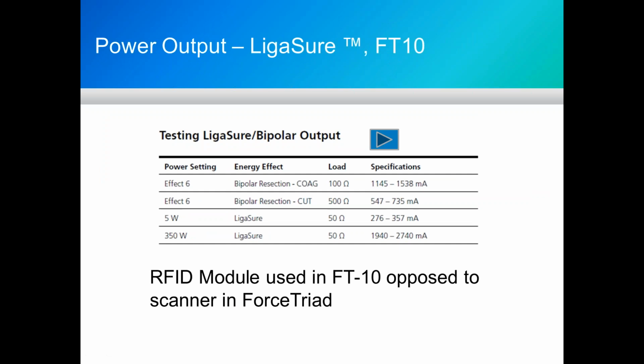So next we're going to test LigaSure. Ligature is a form of a bipolar output. It is actually going out, as all of these tests really do, in a true procedure. The generator is acting in a closed loop mode, so it's monitoring the tissue resistance. And of course, tissue will increase in density as current starts to flow through it. And in LigaSure mode, we're using that to determine how much power to put into the vessel sealing device.